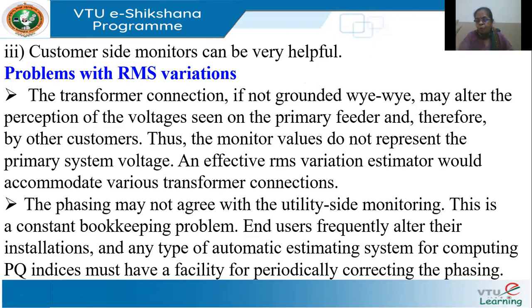And for each of the customers, the monitored values on the primary side may not represent the exact voltages. So when we design an RMS estimator, we have to take into consideration the transformer's connection: star-delta, delta-star, star grounded, delta-star grounded, whatever it is.